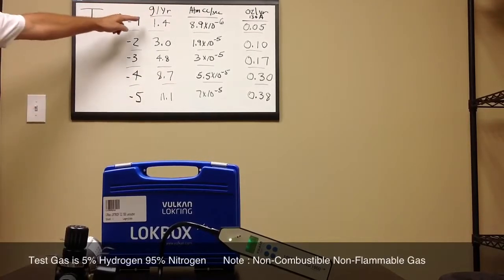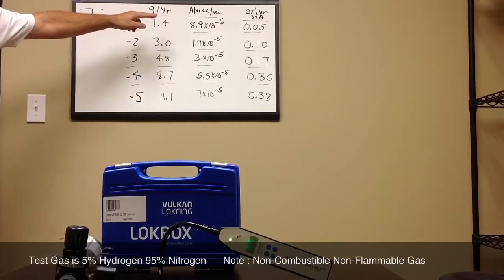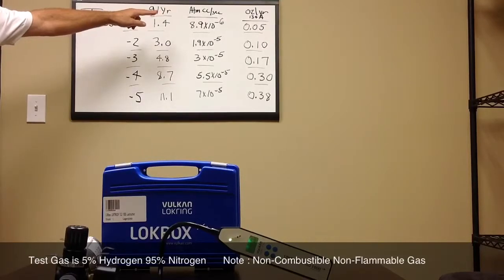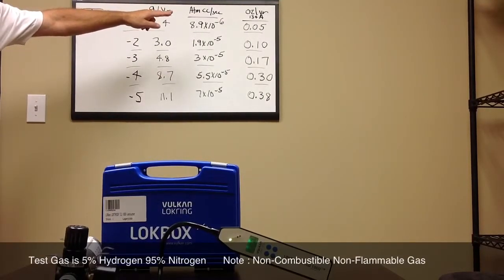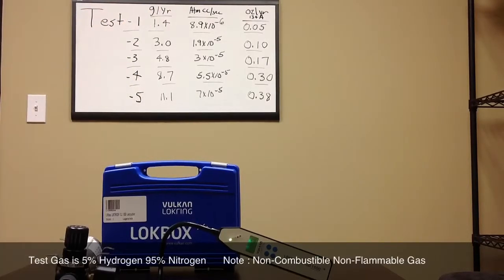First test will be at 1.4 grams per year, which is 8.9 times 10 to the minus 6 on a helium equivalency scale, and then it's 0.05 ounces per year of R134A.